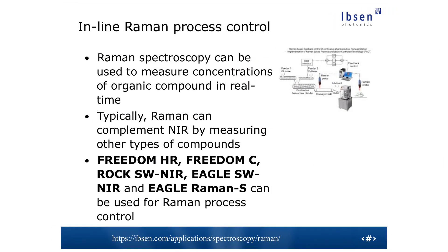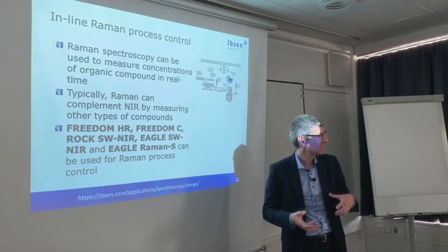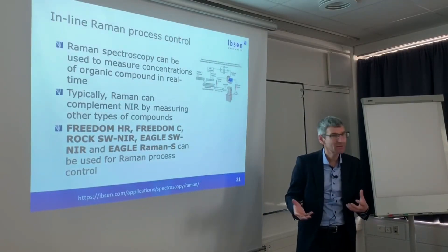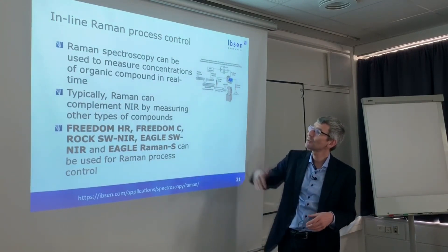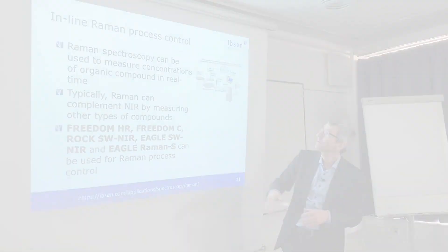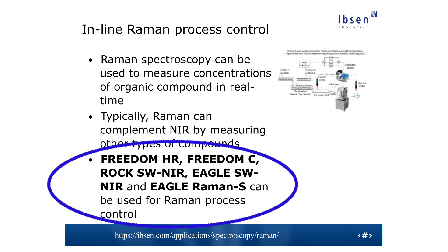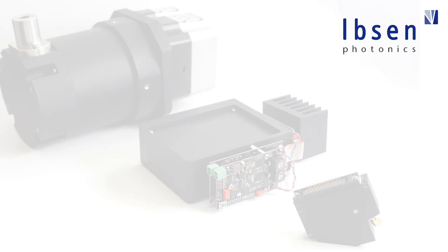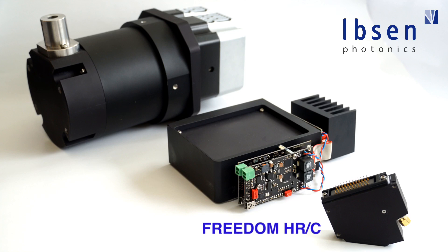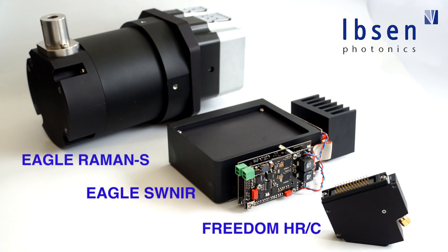Also for inline use — and again this is up and coming, not used a lot yet — Raman is kind of a complementary method to NIR. NIR can see some molecules nicely but not others, and the fortunate thing is that the ones NIR is bad at, Raman is typically better at. So some will combine the two, or some will simply use Raman instead of NIR. Here you have more choices depending on how difficult your Raman signal is. If it's a low-end, easy measurement, maybe you can use the Freedom HR or Freedom C. But if you need really high sensitivity, you move towards the Eagle Raman S spectrometer.